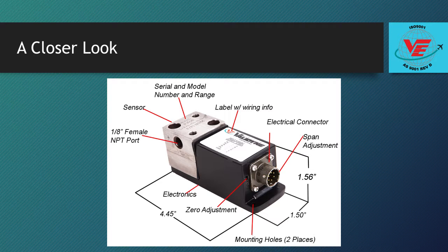The sensor body will have the complete model number and serial number of the transducer etched onto the top for easy reference. There is also a label on top of the electronics housing that has the wiring information for that particular transducer. The pin connections for the power and signal are identified here. The electrical connector is mounted on the rear of the housing and is typically an Amphenol PT02A 6-pin military-style connector. The mating connector is available from Validyne and is ordered separately.